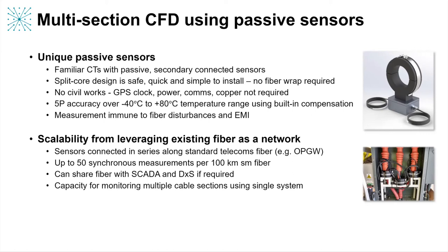Each one of these sensors is very safe, quick and simple to install because each component is very familiar to installers in the industry. Because each sensor is passive, there's no civil works required for installation — no auxiliary power supplies, active telecoms or GPS outside the substation. Each sensor has a very wide operating temperature range, and each sensor will also passively tell us its own temperature, which allows us to actively compensate for any temperature changes in the data generated by the interrogator.